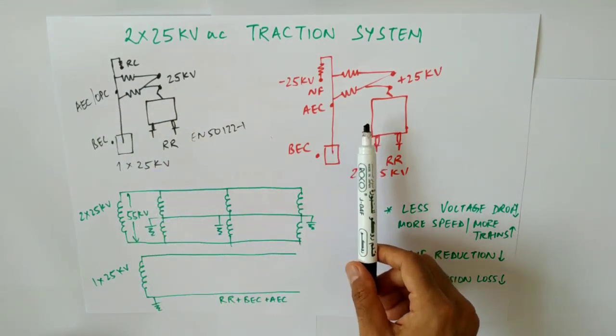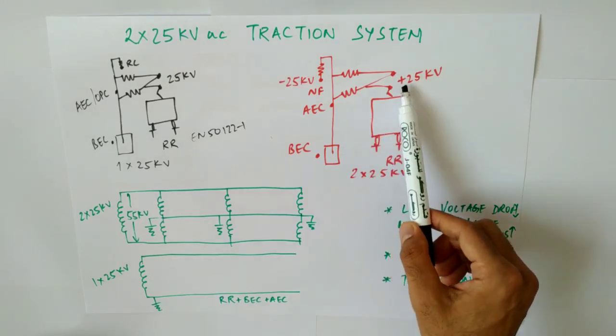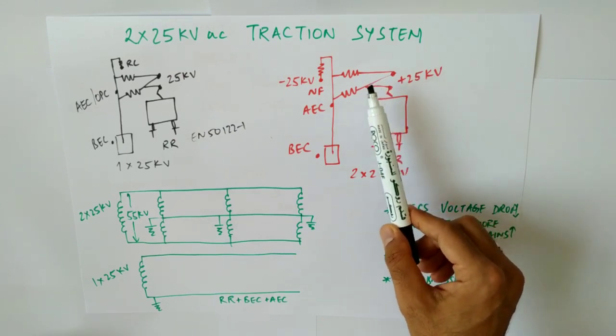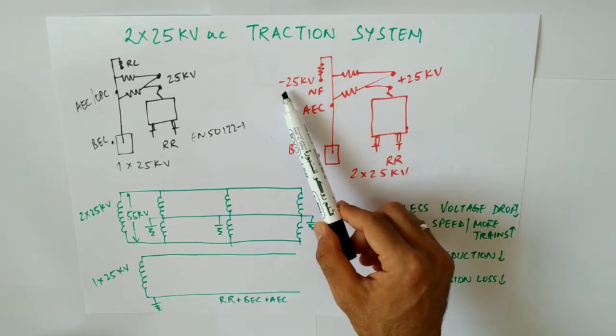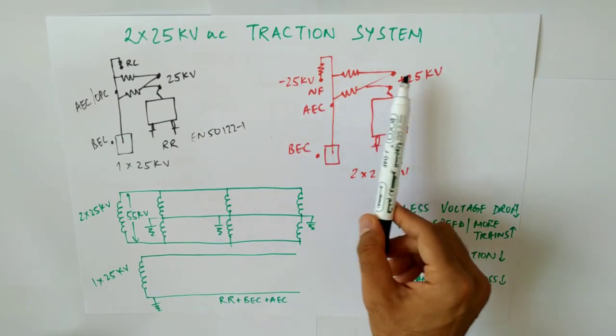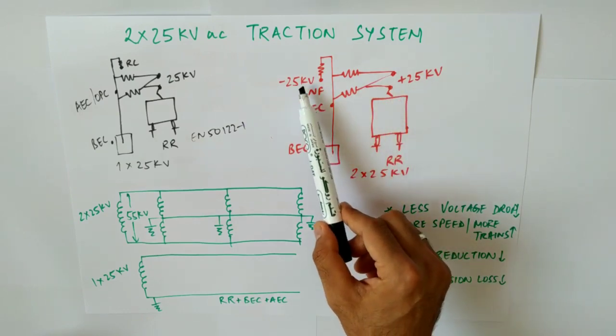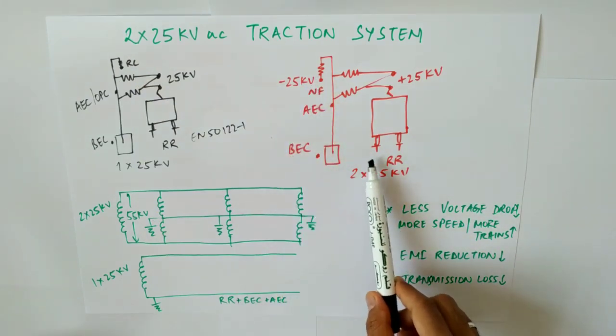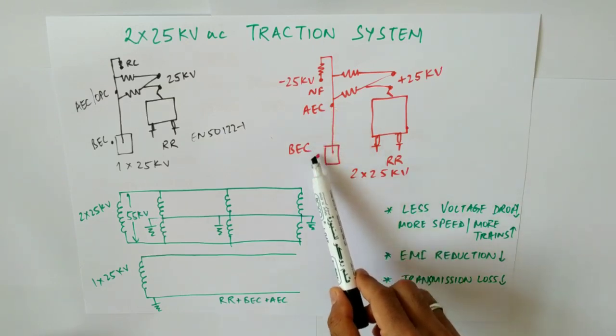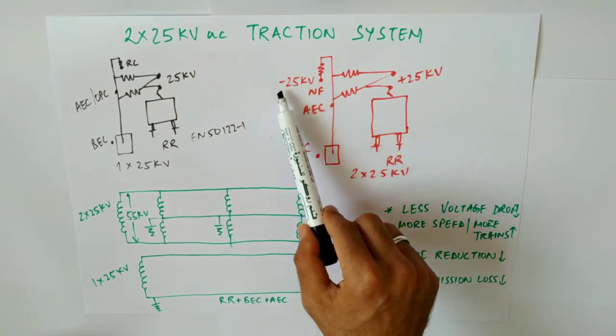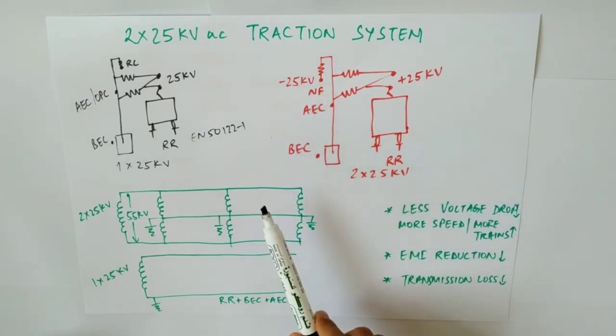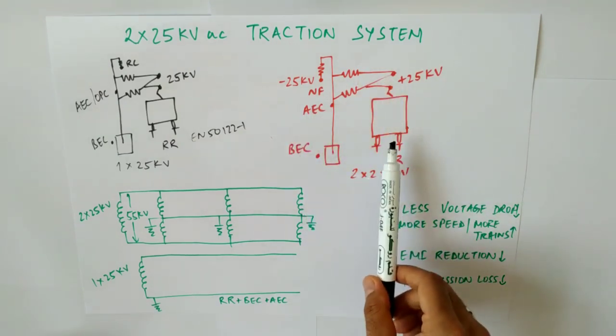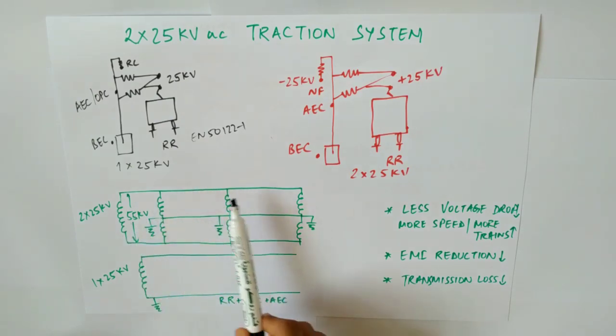In the 2×25 kV system, the contact and catenary system is again at 25 kV — it is not at 50 kV, it's at 25 kV — and then there is another feeder called the negative feeder, which carries minus 25 kV supply. That is why this system is known as 2×25 kV. This negative feeder acts as a return feeder carrying the return current, just like the RC in the 1×25 kV system.